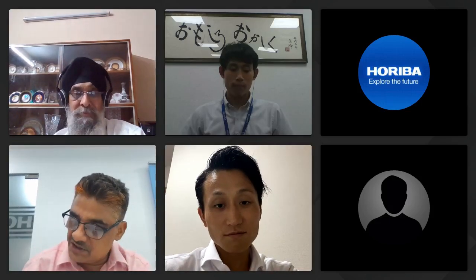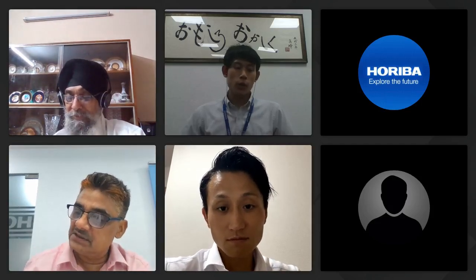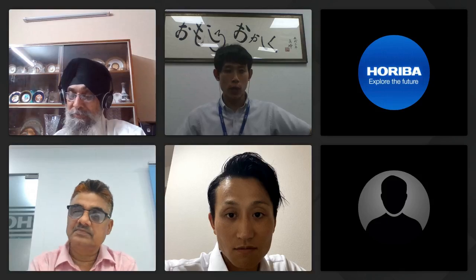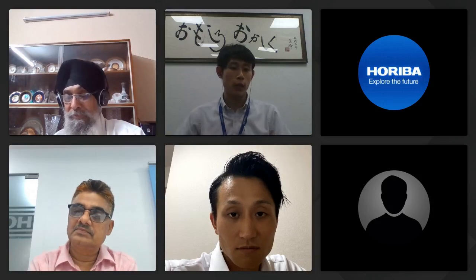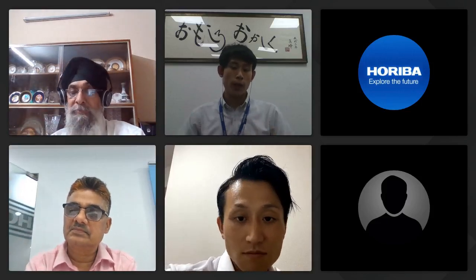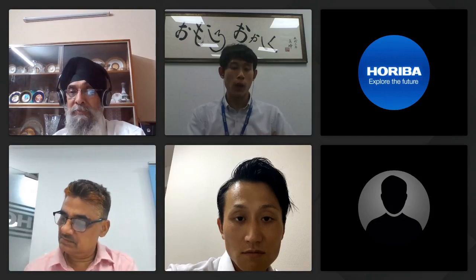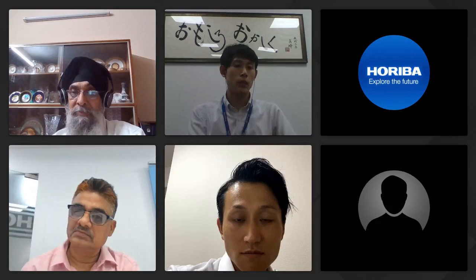This again is a question, but I think you already answered it, about the calibration. How does AutoZero ensure calibration? Okay, AutoZero calibration: once in a while, when there's a drift in the reading, you have to do a zero calibration. But in this case, for zero calibration, you have to flush the system with clean water, depending on the country, or tap water or something. But by having automatic zero calibration, when there's a drift, it will actually perform the calibration automatically during a specific time set by the user.